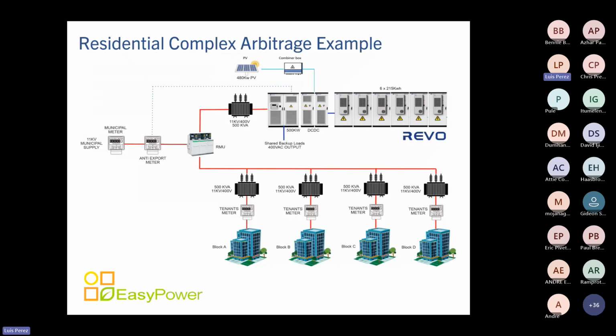So this is how this looks in a graphical format. You will have your supply from the municipality. The municipality builds a sectional title at that point, after which it goes to an existing RMU that distributes via high voltage, medium voltage wiring, mini subs all around the complex, and that essentially supplies each and every one of the tenants. So there will be a metering bank on each and every one of those building blocks. Then on the other end, you have a mini sub, which is next to the RMU and is connected to an inverter, a PCS. In the case of this PCS, it does have solar input.